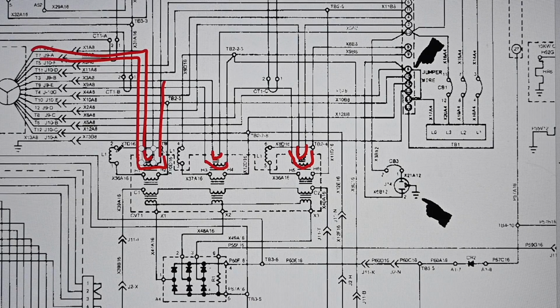As a heavier load is applied to the generator set, more current flows through those wires, setting up a higher voltage induced in the transformer, known as a current boost function. It helps with voltage regulation by setting up a higher voltage within the magnetic amplifier, assisting this primary winding right here. The same thing happens over here and here. These windings are just a couple turns of the very heavy gauge wire that comes off the generator's stator.